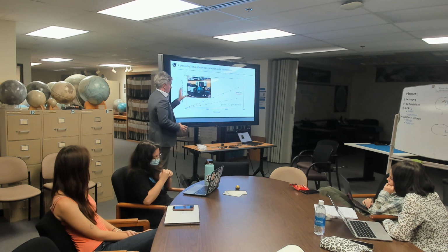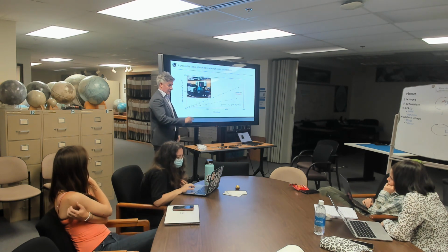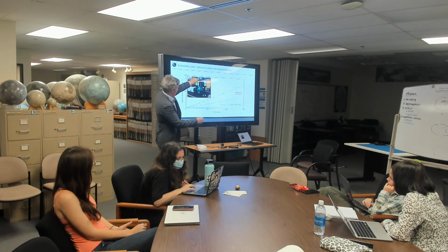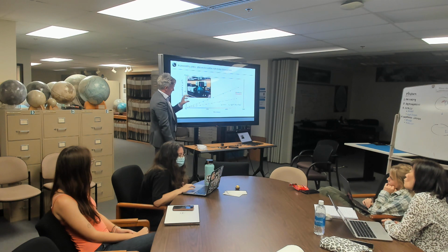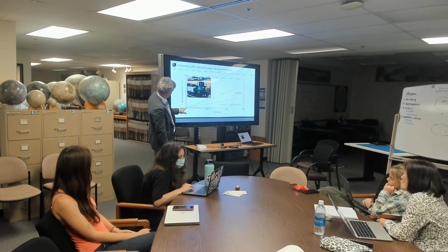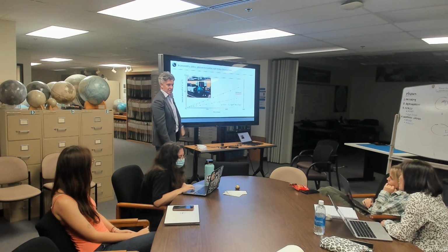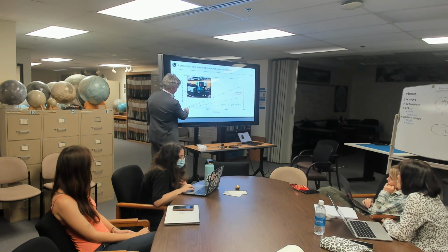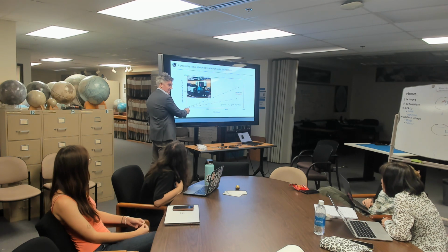What I then do is I just put my instrument in front of this hole, and I turn my instrument on, and I turn the light down. I turn these knobs all the way to the right. It's pretty dark in this hole. And I point the instrument in and I say, well, I know the spectral radiance in here is this number, less than 1. What's the DN that the instrument is telling me? And the DN is, I don't know, it's like here, that's 50. And I just plot.